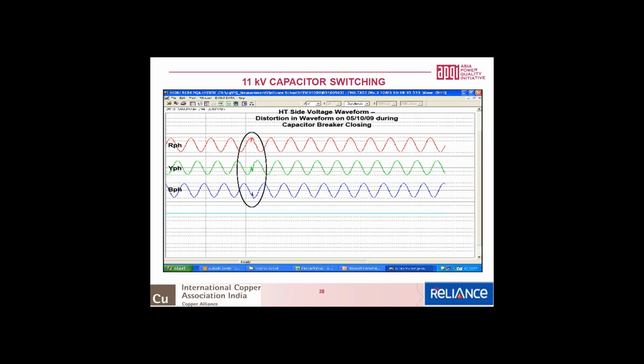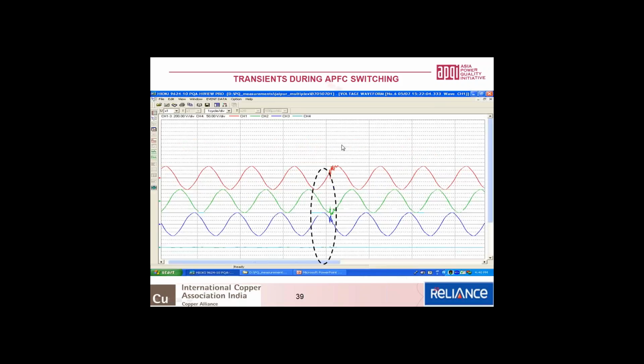Similarly, with our conventional APFC, every time the contactor switches, you can see the notches appearing in the voltage waveforms. If the connected equipment continuously experiences this, it might experience some problems. Therefore, you have to be very, very careful, as the APFC is extremely close to the load center.